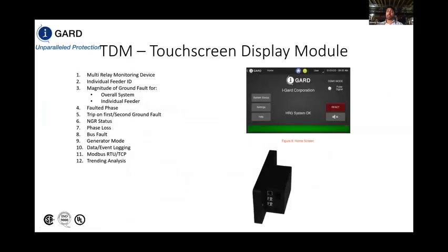This touchscreen display is very intuitive and useful to use in providing information to maintenance and end users on how much magnitude of ground fault there is in their overall system, how much ground fault there is at each individual feeder. We can indicate what phase is faulted. We can trip on first fault or second ground fault, depending on your preference. We can indicate phase loss. We can indicate a bus fault. We can provide the data and event logging on all of the incidents that are occurring in the system, and we can provide that information via Modbus TCP IP as well.